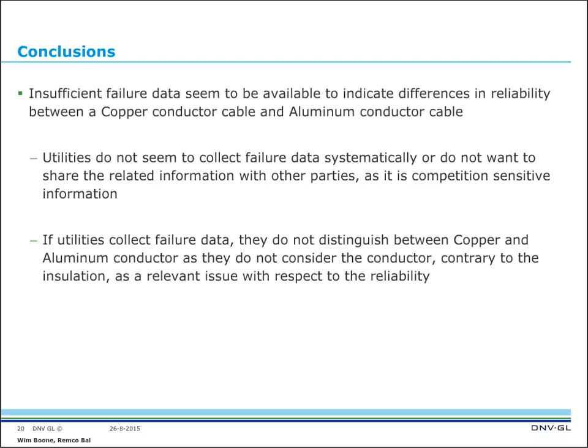Copper conductor cables are preferred technically because of lack of problems with connectors, easiness of installation, better mechanical properties, and smaller radial size. For that reason, there are still all-copper utilities. However, their number is decreasing. Aluminum conductors are mainly selected for economical reasons, but additionally advantages like lower weights and compatibility with existing cables are mentioned. The utility industry seems to be insufficiently aware of the technical superiority of copper and is more focused on the initial costs, as the LCCA shows a minor difference between copper and aluminum.